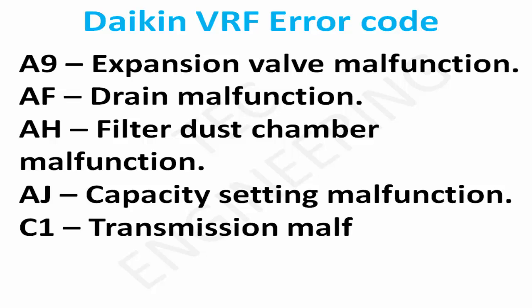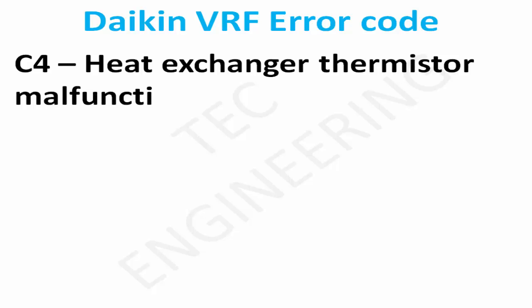C1: Transmission malfunction between main PCB and sub PCB, indoor. C4: Heat exchanger thermistor malfunction, indoor.